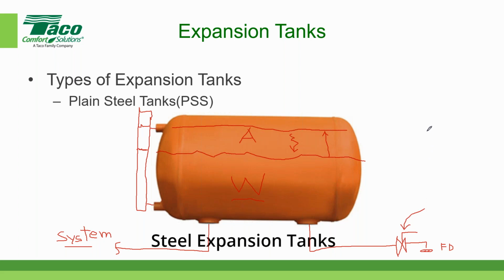That's a great question. It gets ugly. On the piping system, there will be devices that allow air to enter the tank and ultimately displace some of the water in the tank. But over time, as the water level rises up the tank, the air gets compressed and the pressure inside the tank increases. So when we open the blowdown valve, the natural expansion, because the water is under pressure, forces the water out and the air expands a little bit. That's how air gets back into the tank. There are devices in the piping system that allow the air to enter the tank, and also when you're blowing down, the air will expand and displace some of the water. Good question.